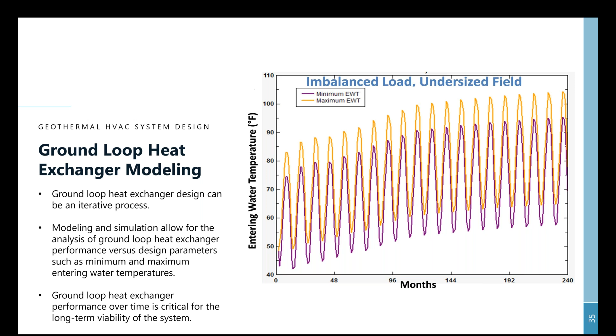So the idea of what we're trying to establish by modeling the ground loop heat exchanger is how we can get stable operation over a very long period of time. Now, I mentioned earlier your minimum entering water and maximum entering water temperatures. The space between those two is what we refer to as the bandwidth of the geothermal field. And what we're trying to do is optimize how much of that bandwidth we're actually utilizing. In the image you see on screen, we're operating between about 40 degrees and 90 degrees Fahrenheit, but our minimum temperature is actually down at 30.